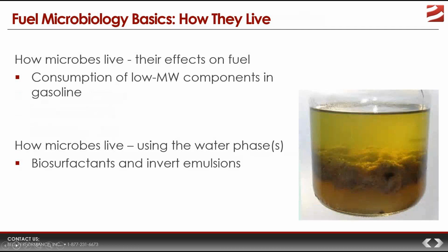Now, for years, the industry thought that microbes did not like to grow in gasoline because the industry thought that the lighter or the lower end hydrocarbons that were in the gasoline mix, we're talking about the 4 carbons, the 5, 6, and the 7 carbons, C4 through C7, were actually toxic to microbes. Now they know that this was not even close to being right. They know now that there are plenty of microbes out there that love to consume these. They chew them up. They eat them for fuel.